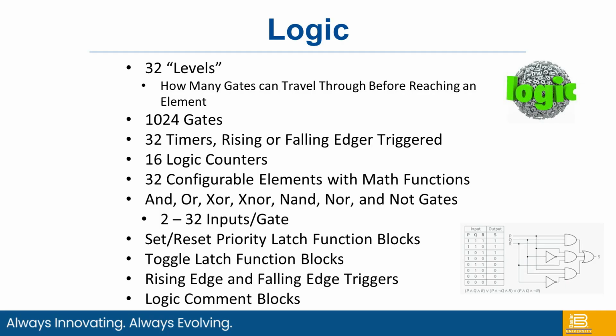Some more on the logic. There are 32 what we call levels. There are many gates that it can travel through before reaching an element. So you can have 32 AND, OR, NOR, timers, functions, and blocks, but then after 32 it needs to hit a gate. What's nice is once you hit that gate, you can use that gate to go back into further logic. So there are multiple layers of logic that you can put in.